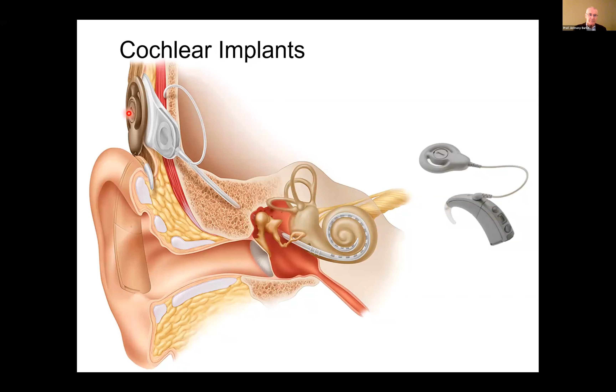The cochlear implant itself consists of a couple of different components. This is the external component. So there's a microphone here, batteries, and a lot of electronics, all miniaturized, goes into this component, which sits behind the ear and is connected to this transmitter that transmits the electrical signal through to the implanted components that we see here. So there's an inductive coil that picks up both the power and the signal that are sent from the external components. The signal is then decoded; there's an encapsulated electronics compartment here.